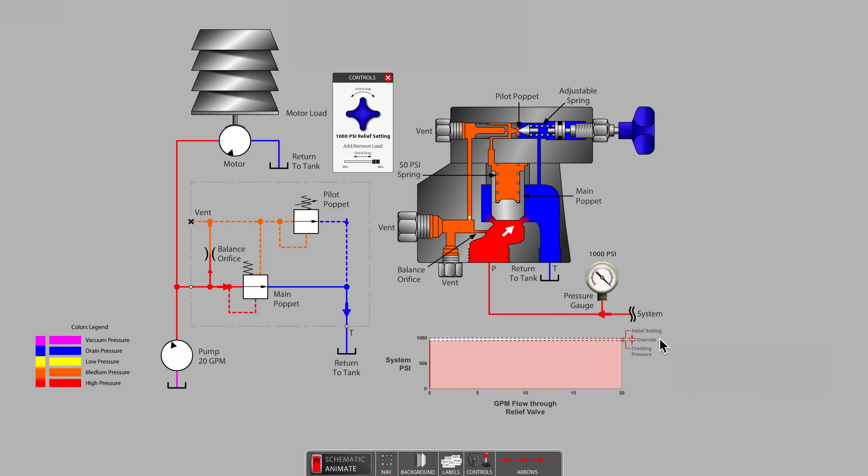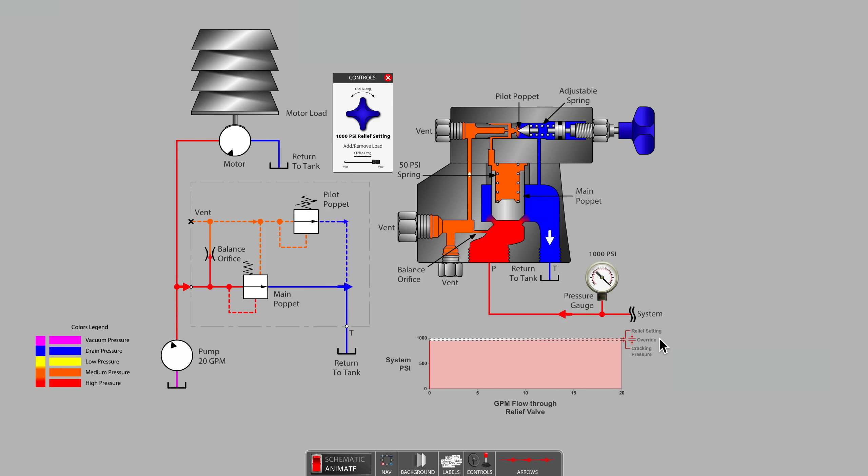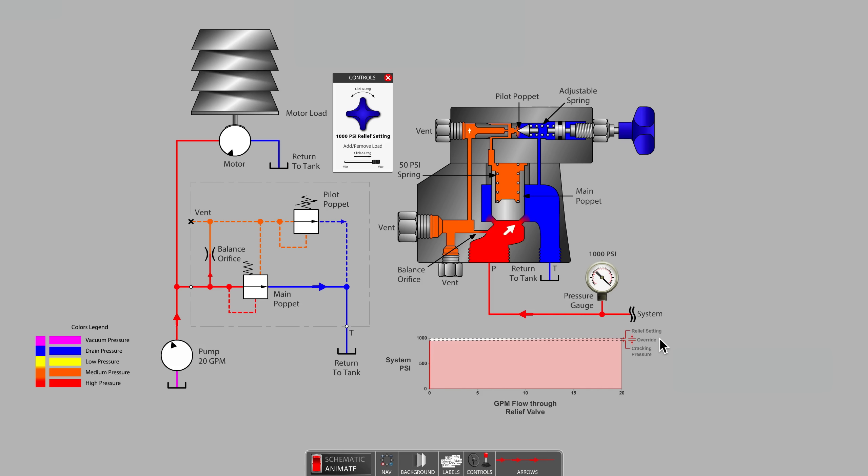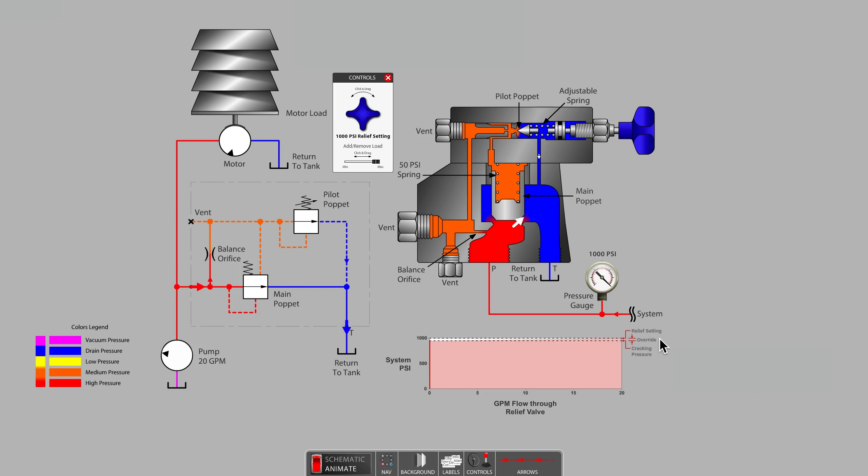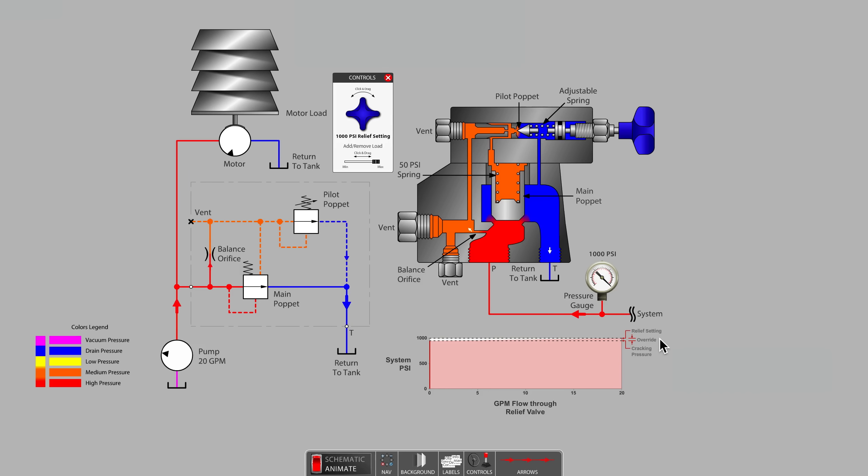The advantage of this type of valve is that it only needs to be set for a pressure slightly higher, 50 PSI higher in this case, than the maximum system pressure, where normal flow rates are still required. This advantage saves input energy consumption for the hydraulic system, it prevents excessive heat build-up, and can also help minimize high pressure safety risks.